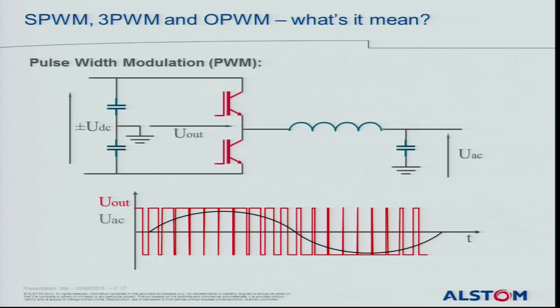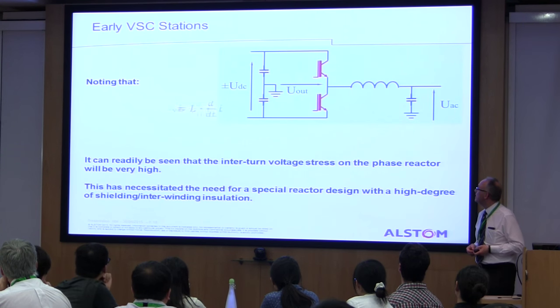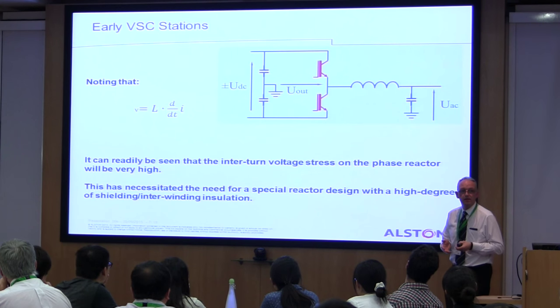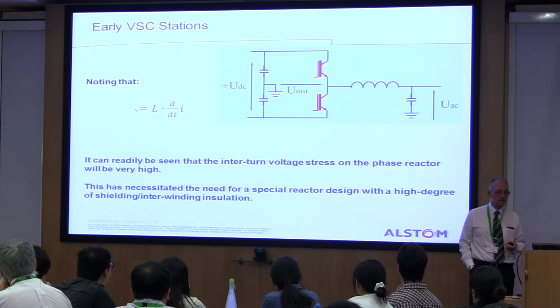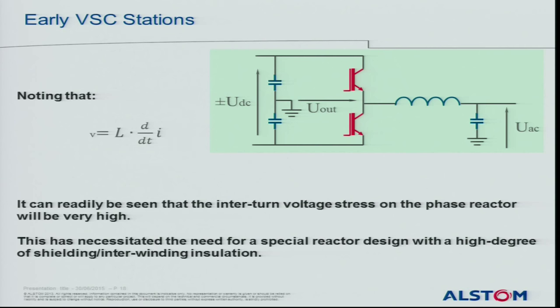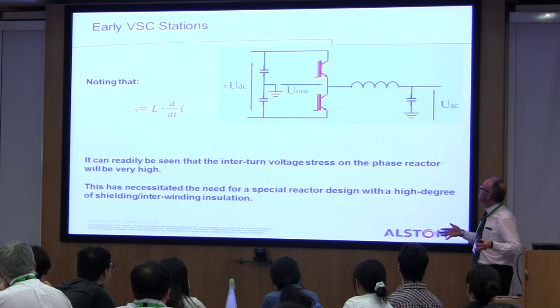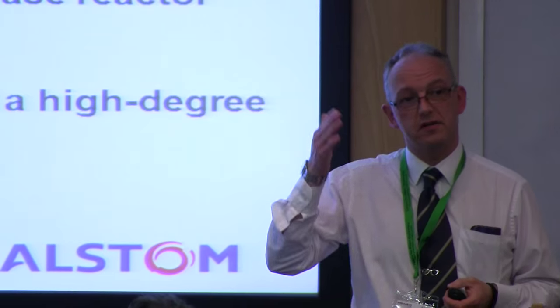PWM — that's a nice simple circuit, but in reality that power converter is smothered in filtering and reactors. That reactor in particular is a very special animal, because the inter-winding capacitance means the voltage stress on those windings is very high and it's a very difficult, bespoke reactor to build. If you look at one of these two-level converter stations, they're just great big tin boxes with shielding everywhere, because there is so much radiated interference from the switching of the converter.